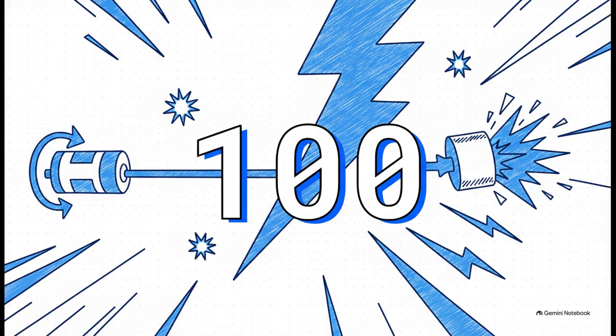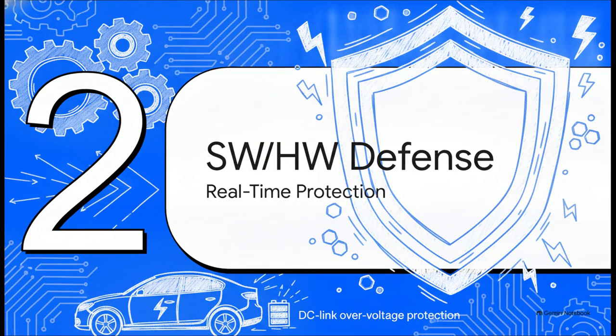Less than 100 microseconds. That is the terrifying speed at which this disaster unfolds. When a load dump occurs, the massive demagnetizing energy from the motor floods directly into the DC-link capacitor. Without any warning, a standard 400-volt system can spike past 1,200 volts in the literal blink of an eye. It breaches component tolerances instantly, destroying vital power semiconductors before even a standard computer processor could process what went wrong.